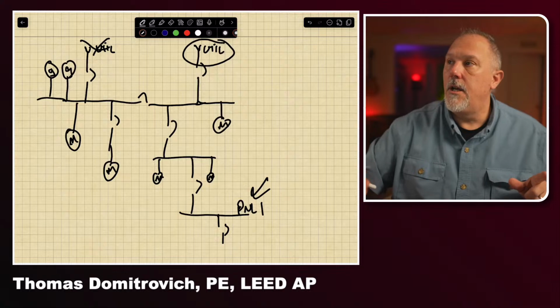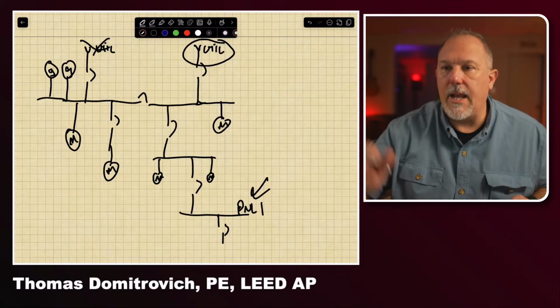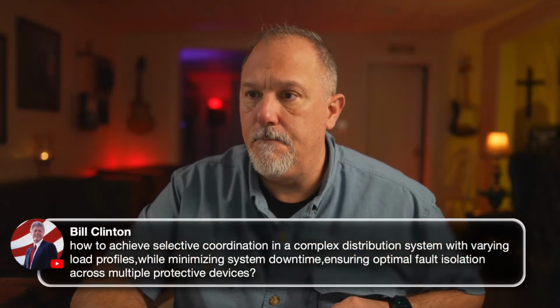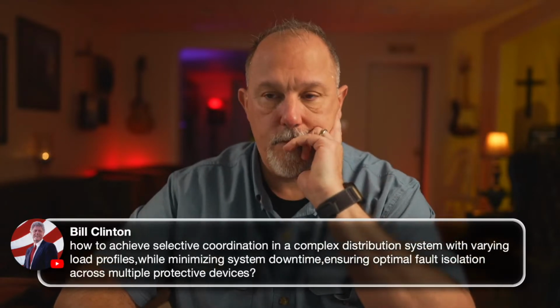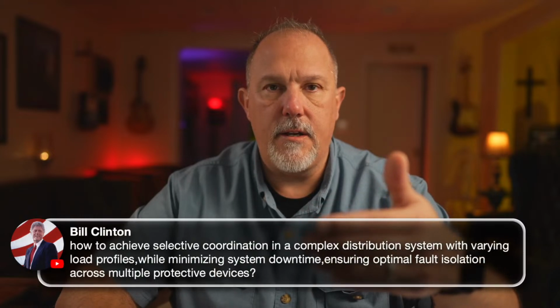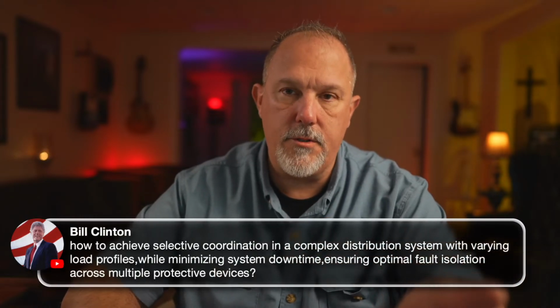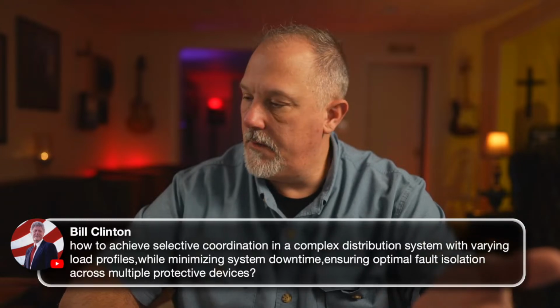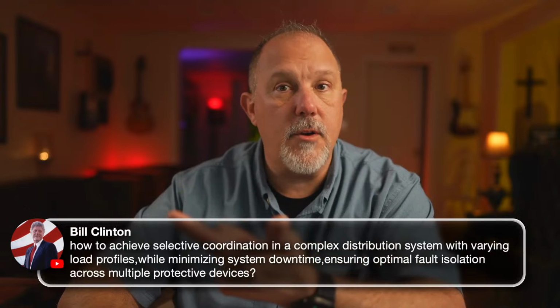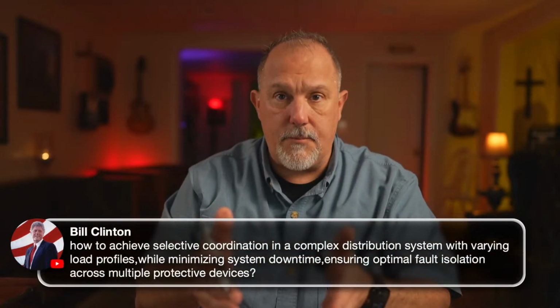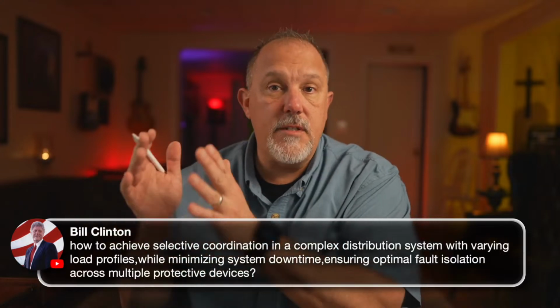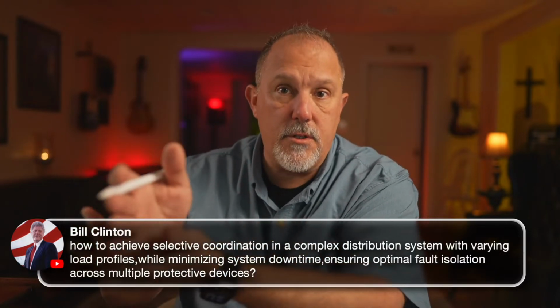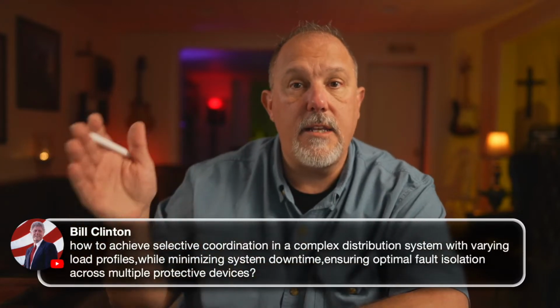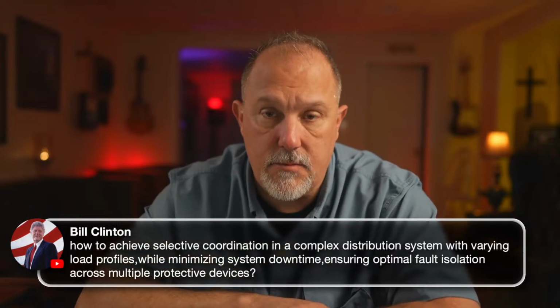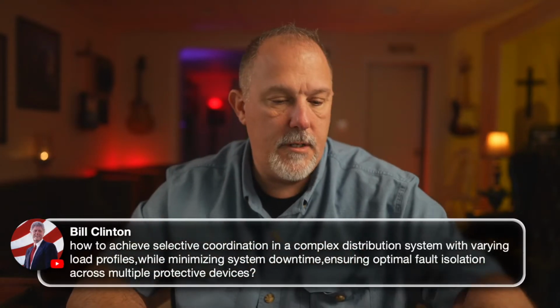All right. I'm not worried about the fault currents, and the complex systems basically are going to be driven by the sources, not necessarily the loads, unless they're motor loads. And then, Bill, I would do my analysis with my time current characteristic curves, and I have to maintain my separation in the overload regions. Then I have to deal with the available fault currents by either using the tables or adding delays and keeping the available fault current outside of the instantaneous region. So that's how I would address that.